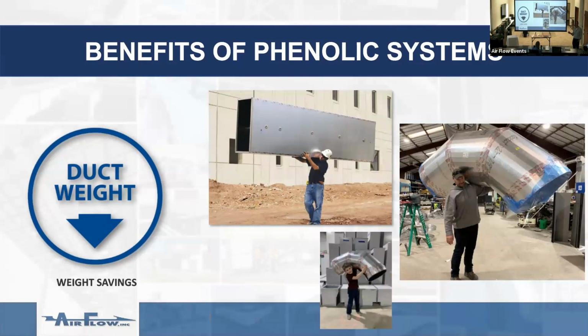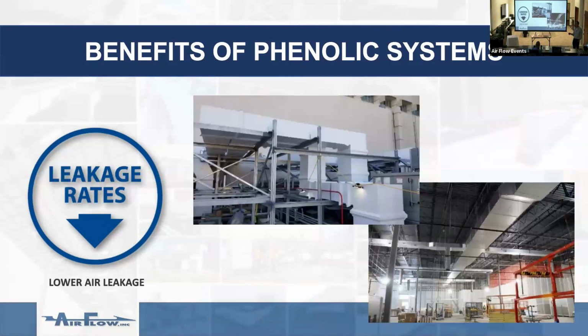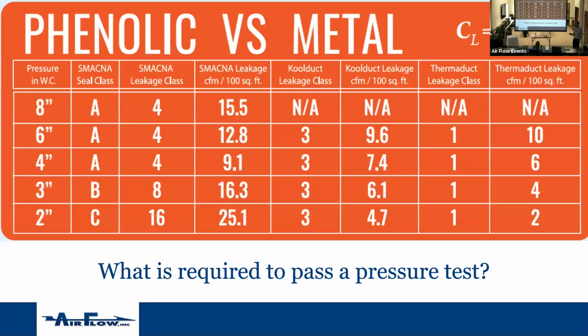But it's somewhere between 1/8 and 1/4 of the weight of metal. So there are some advantages. And of course, it's insulated. The insulation is the duct. We already talked about leakage rates. The leakage class for all the outdoor duct product that's vinyl clad is 1. So super tight. We talked about this. I actually made my chart wrong. It's 1/3 of this number. So leakage class, or leakage in 100 square feet, is 1 point something, very low per 100 square feet.